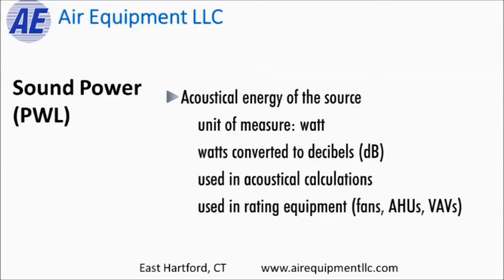An important measurement in acoustical science is what we call the sound power level. The sound power level is a measurement of how much acoustical energy is being emitted by a noise source. We measure sound power in watts but quickly convert it to decibels, which is a much more easy unit of measure to work with. Sound power level is a crucial piece of information for any acoustical calculations, and it's used to rate equipment such as fans, air handlers, and VAV boxes.